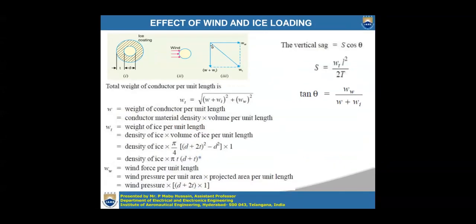When there is wind and ice loading on the transmission line, the total weight of the conductor will be a combined value. W is the weight of the conductor per unit length, Wi is the weight of ice per unit length, and Ww is the wind force per unit length — all in per unit length values, either per centimeter or per meter. The weight per unit length may be given directly, or sometimes the conductor material density and volume per unit length are given.